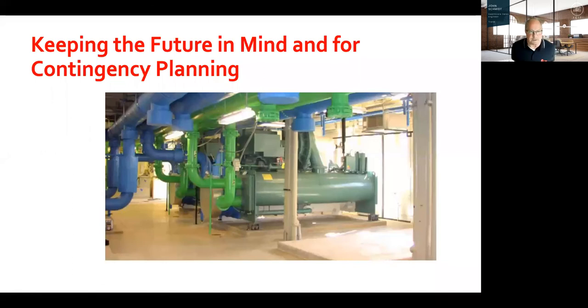Finally, along the lines of redundancy, if you're planning on building a new plant, put in an extra set of pipes. The blue pipe and the green pipe above that empty pad there are examples of where we could tie in for that rental chiller should that be needed. And when you're building this new plant, it's going to be millions of dollars. So to add another 1,000 square feet and a little bit of extra piping for the future, in case the hospital load grows, which most of them do, and also for that contingency cooling in the event of a major catastrophe. Next slide.